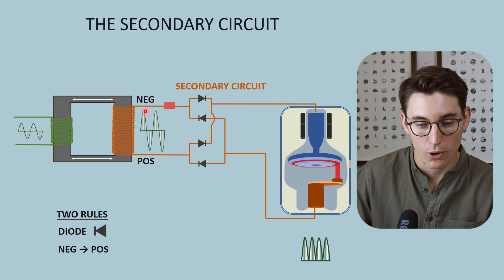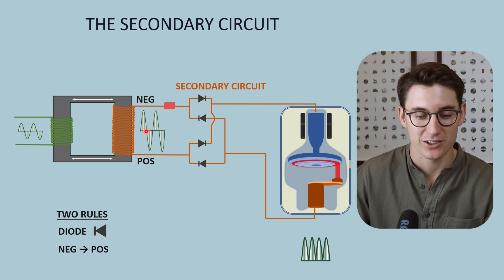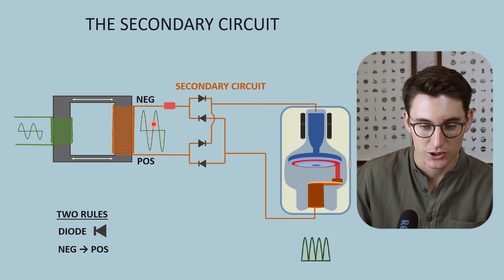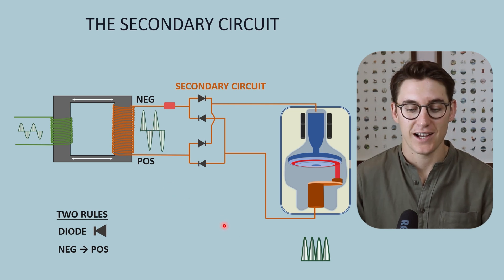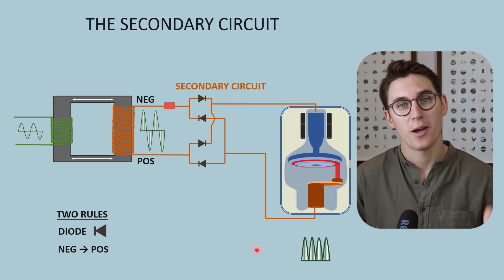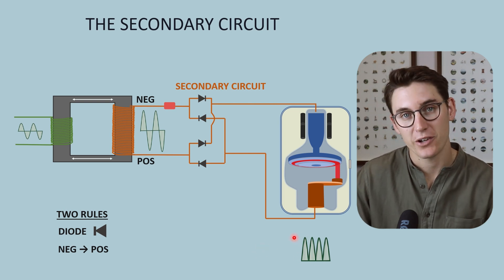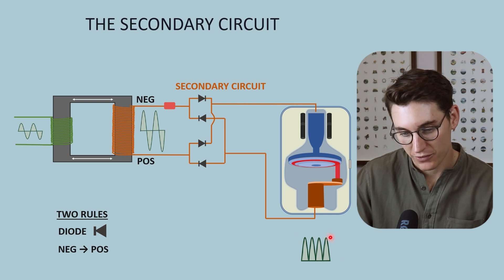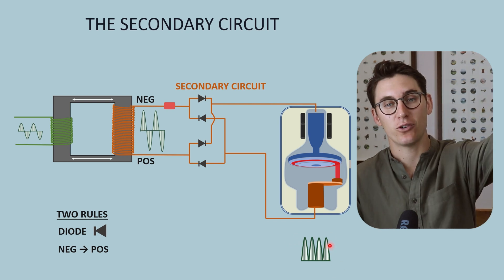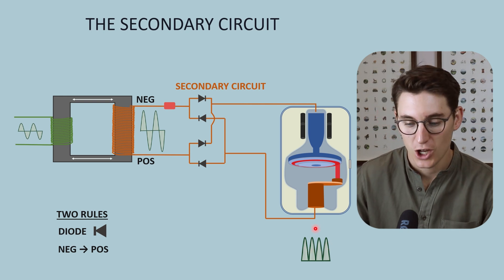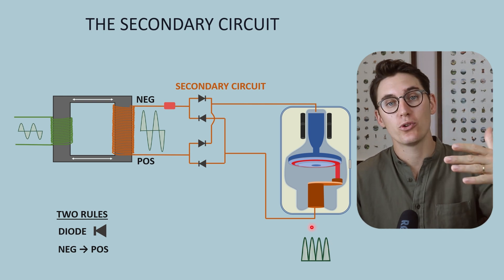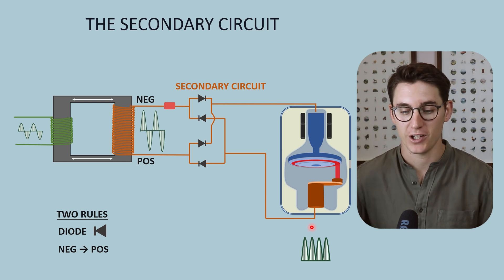We've ensured our positive deflections stay positive and we've converted our negative deflections into positive deflections. However, this rectified current is still fluctuating — it has periods of peak voltage as well as periods with no voltage. We want to create a smooth, constant tube potential between our cathode and our anode, and that's where the process of generation comes in.